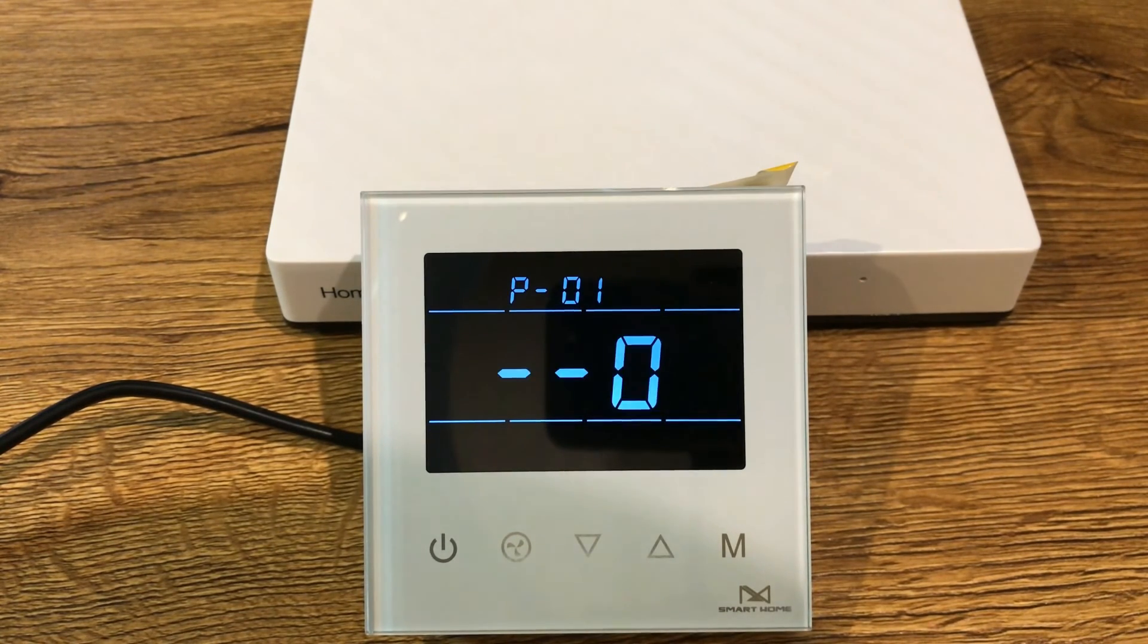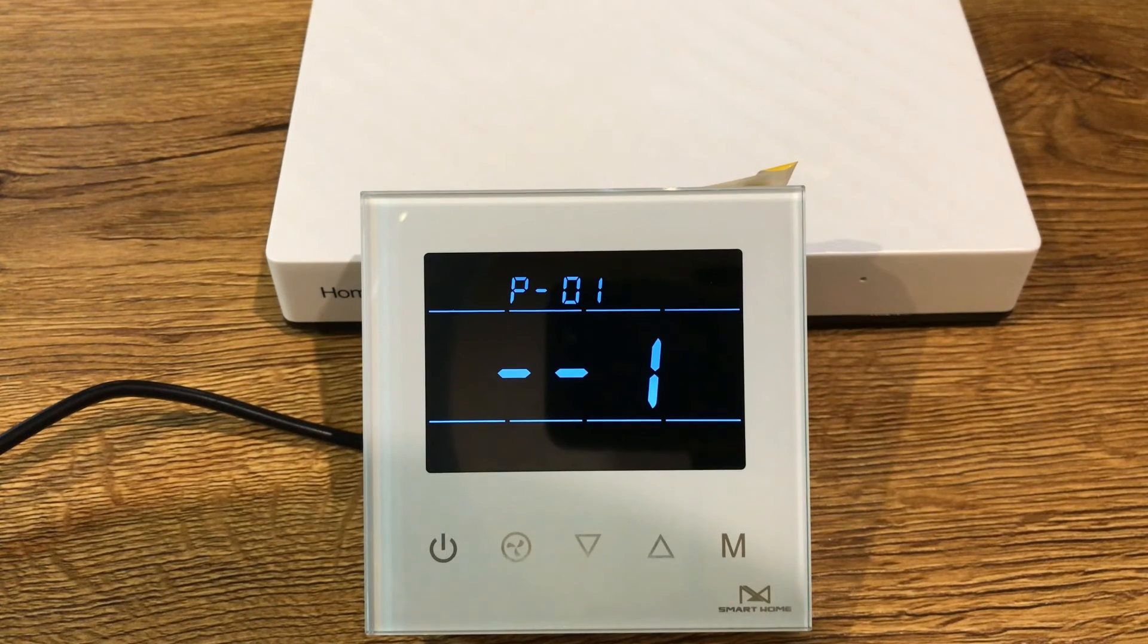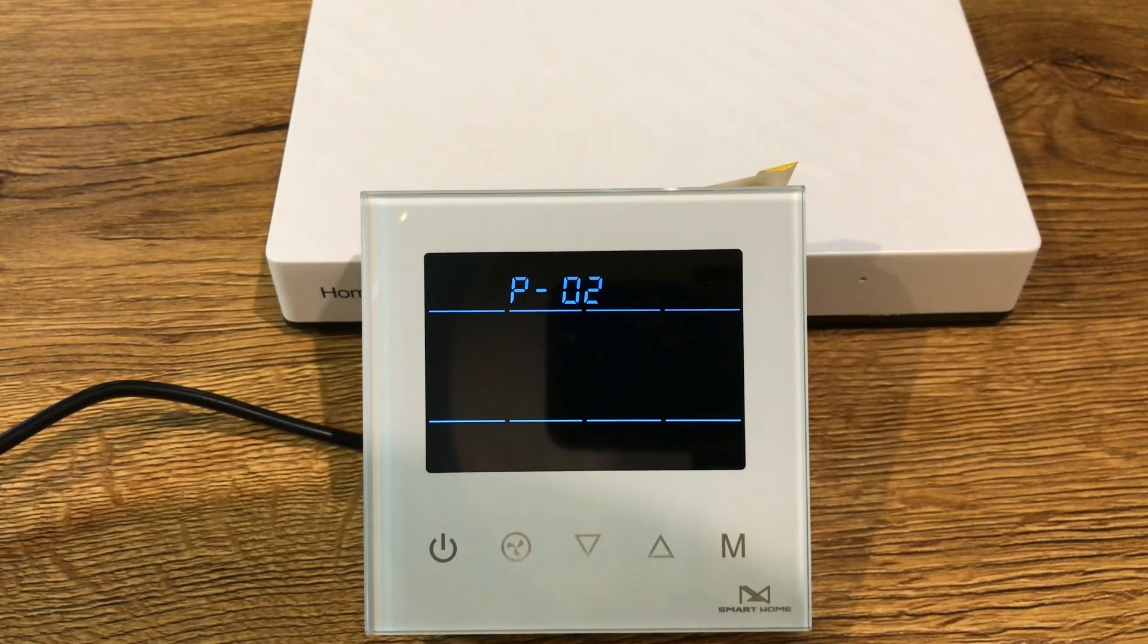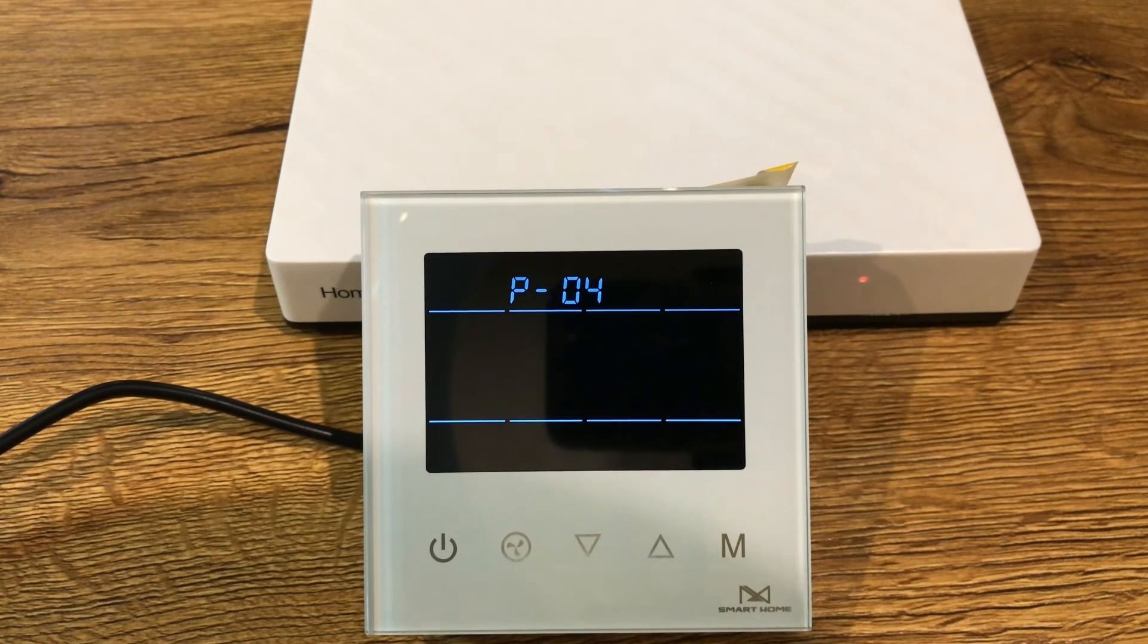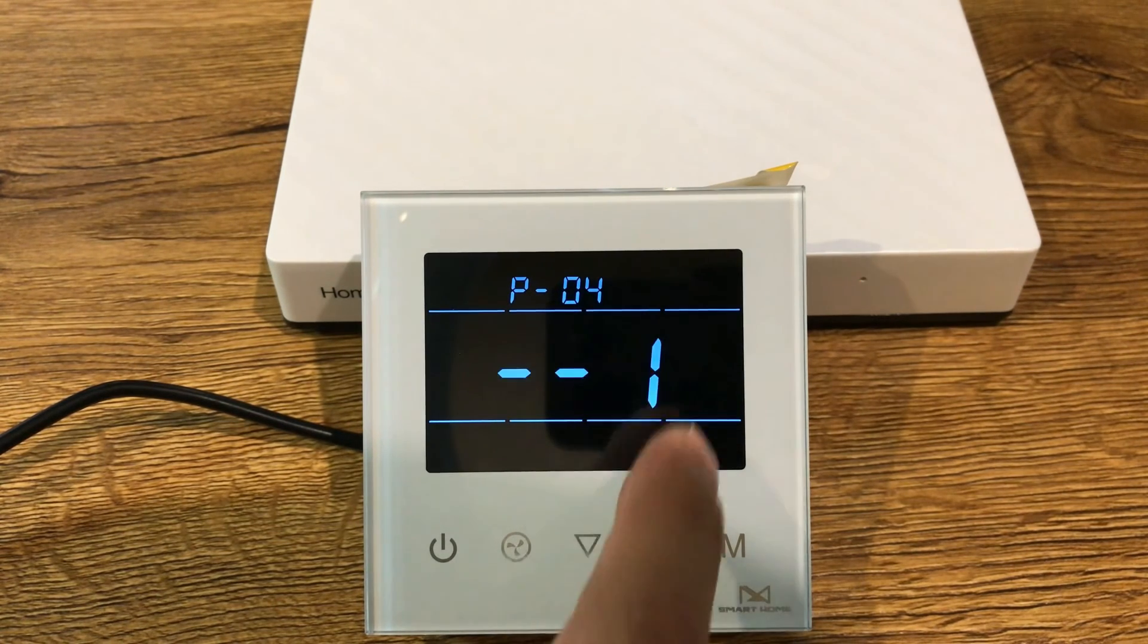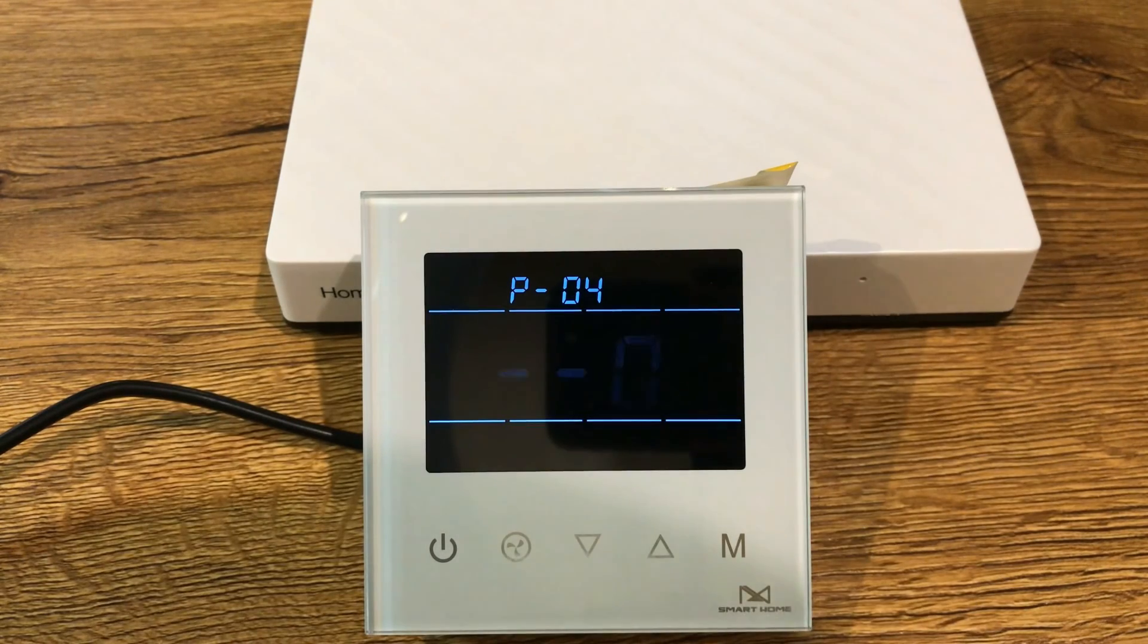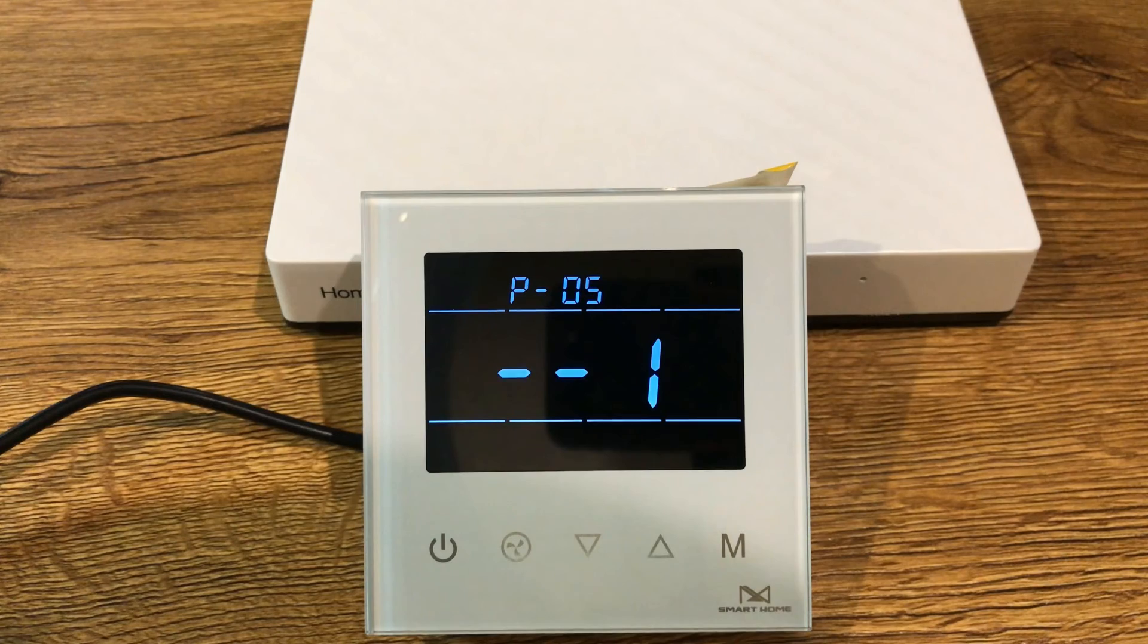Parameter number 1 is screen brightness. 0 means dim without key touch, 1 means always on. Parameter number 2 is related to fan work mode. Parameter number 4 is temperature unit. 0 is Celsius, 1 is Fahrenheit. This is the unit displaying in thermostat display. Parameter number 5 is related to the beep sound.